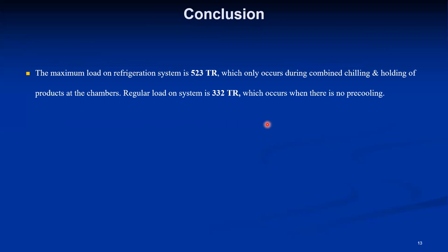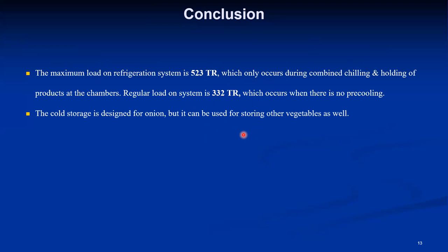The total heat gain is the addition of all four load types, coming to 1,593.26 kilowatt. Ten percent of that is the motor load — 159.32 kilowatt — and five percent safety consideration gives 87.63 kilowatt. The grand total refrigeration load becomes 1,840 kilowatt, that is 523.3 TR. This is the total refrigeration load for storing onion with 8,400 metric ton holding capacity and 1,400 metric ton chilling capacity. The maximum load of 523 TR generally occurs during combined chilling and holding. Without pre-cooling load, the load reduces to 332 TR, which is the regular holding load.